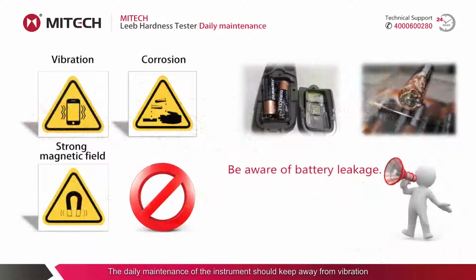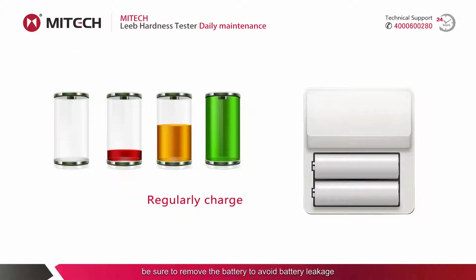The daily maintenance of the instrument should keep it away from vibration, strong magnetic fields, and corrosive media. If it's not used for a long time, be sure to remove the battery to avoid battery leakage. If rechargeable batteries aren't used for a long time, the battery will be completely ineffective, caused by running out of power. So even if not used, the battery should also be charged regularly to avoid damage.